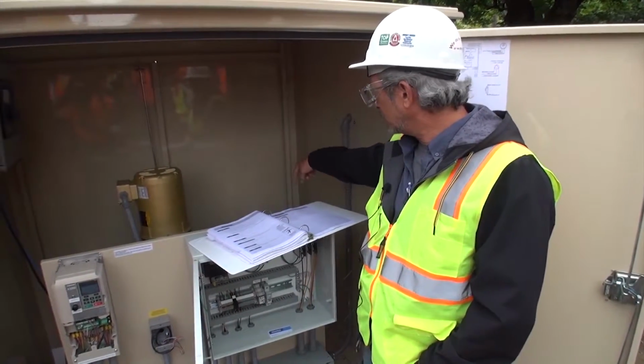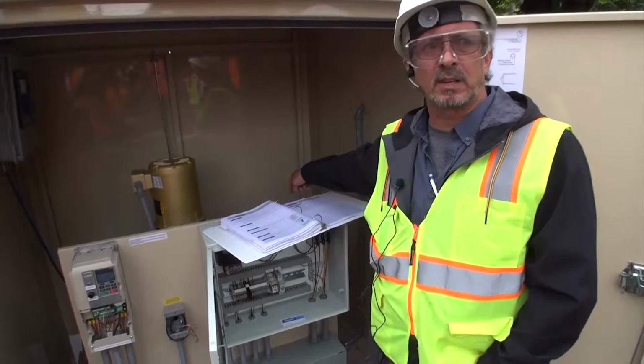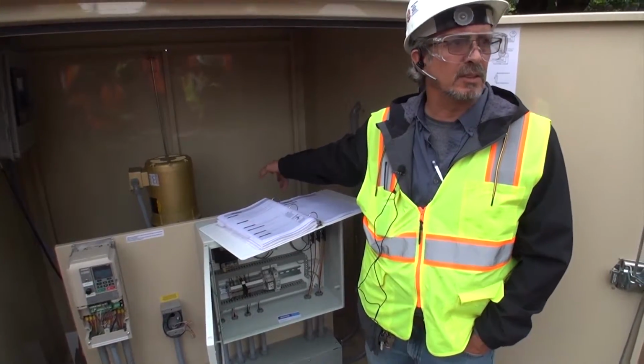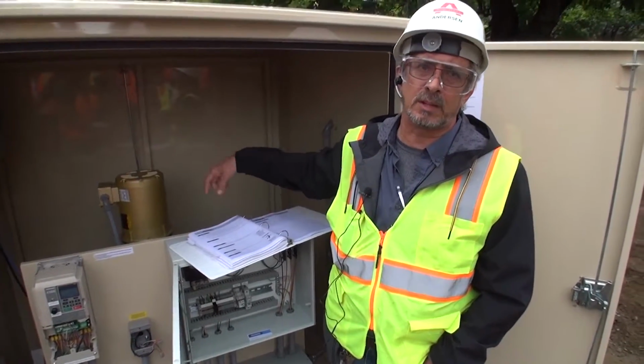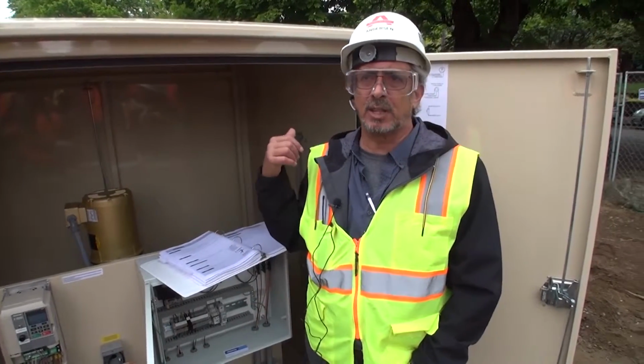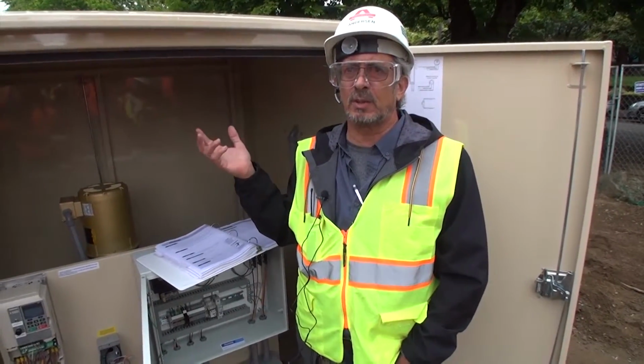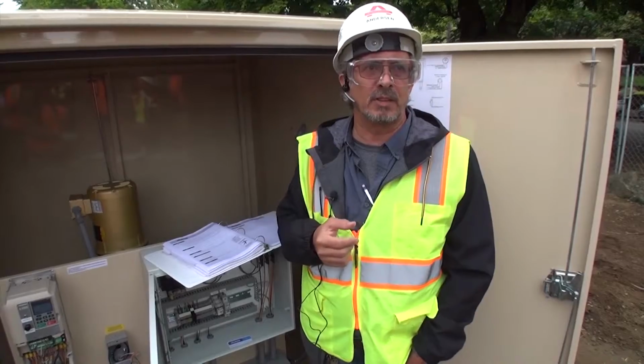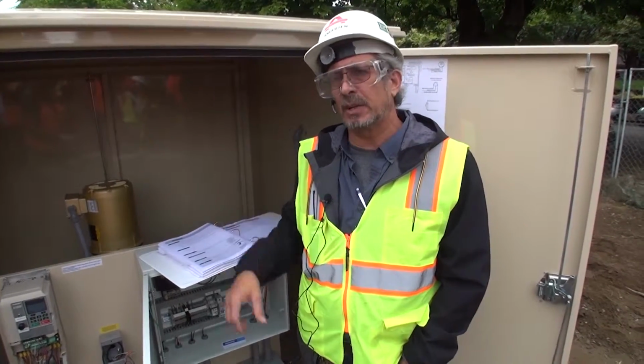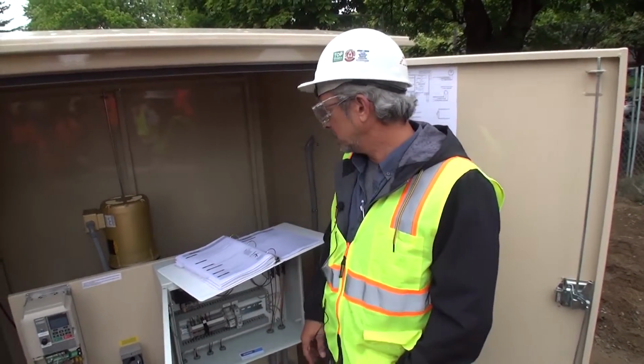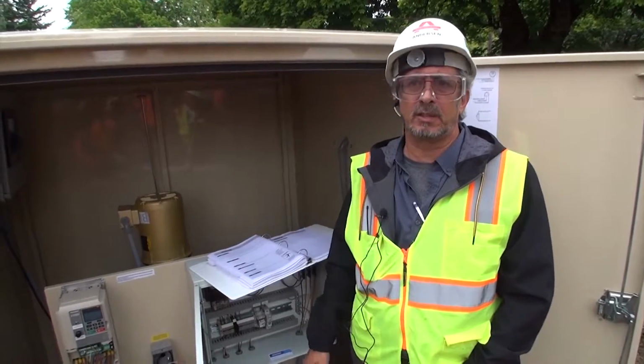The transducer, every once in a while that port's going to get closed. When I say every once in a while, you might have to do this. You're on potable water, you probably won't have to do that, but every 10 years that can actually get plugged. So if you have a situation where you have no water pressure yet it's showing you have water pressure, check and make sure the port's cleared. You're going to have them out once a year anyway, so that'd be a good time to check your port.